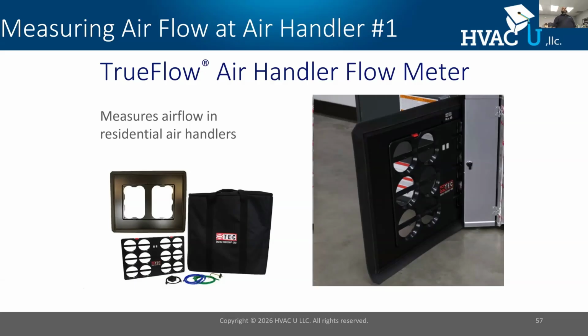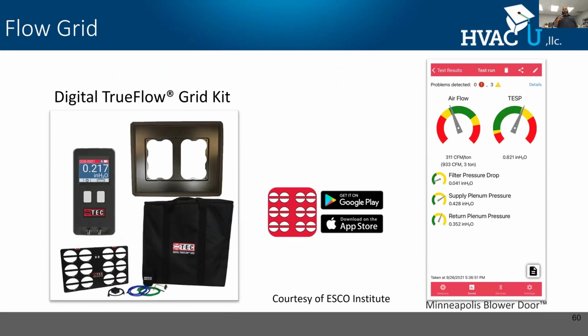So this is a flow meter. Energy Conservatory makes this tool. It's really awesome, not from a marketing standpoint, but I've even seen utility companies start to specify using this tool because it gives you airflow and static pressure really easy. One of the reasons I like it is that it also gives me a report. I can actually show the customer that they have a duct to equipment problem, here's the airflow measurement, and here's why I'm saying it. And it has a red, yellow, green hierarchy. I can tell how I'm doing based on some settings that I can change.